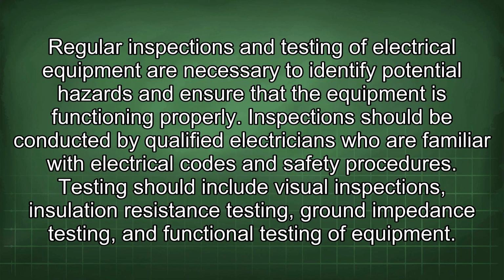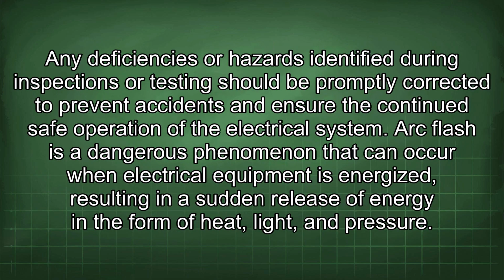Regular inspections and testing of electrical equipment are necessary to identify potential hazards and ensure that the equipment is functioning properly. Inspections should be conducted by qualified electricians who are familiar with electrical codes and safety procedures. Testing should include visual inspections, insulation resistance testing, ground impedance testing, and functional testing of equipment. Any deficiencies or hazards identified during inspections or testing should be promptly corrected to prevent accidents and ensure the continued safe operation of the electrical system.